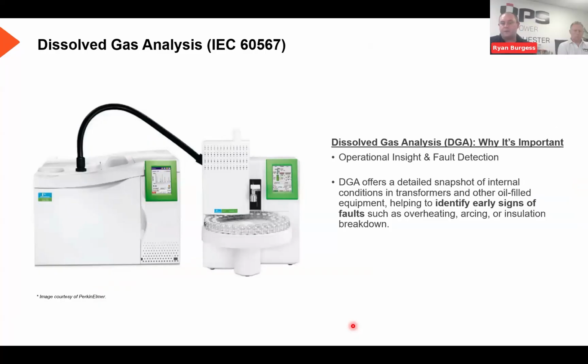So that's the end of fluid quality. Now we're going to look at dissolved gas analysis, known as DGA for short. So DGA is probably the most critical tool in determining how the transformer or the electrical asset itself is performing over time, as it's used to determine the condition and the health through analysing the gases present to determine the types of fault, if they are present. So on the next slide, this will cover what gases we look at.